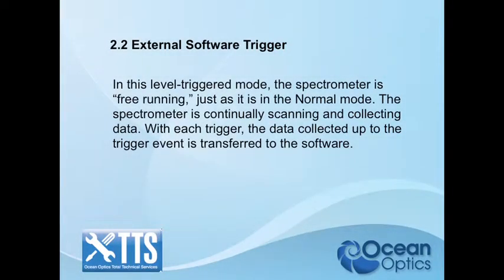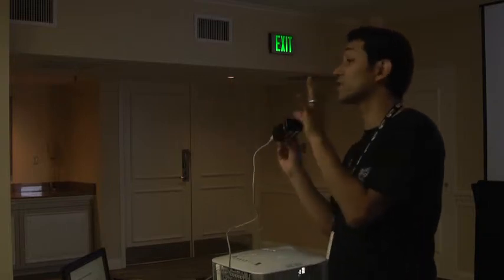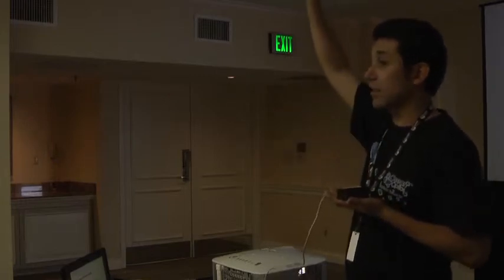The software trigger is a level trigger. As long as you provide five volts, it's going to keep acquiring and updating the spectra on the screen. In the background, the spectrometer is running in free-running mode, acquiring at whatever integration time you set in software. When you send the five-volt TTL signal, it will update the screen with the current acquisition in the spectrometer suite. This is not synchronization — it's simply: every time I send you five volts, update the screen.